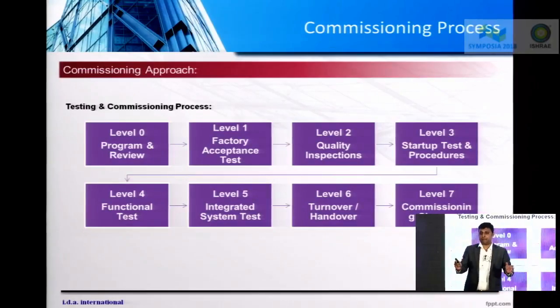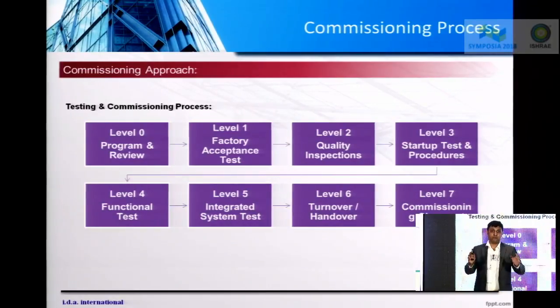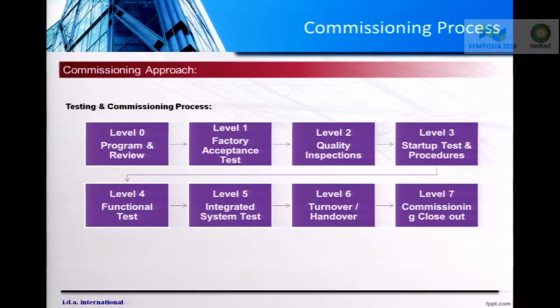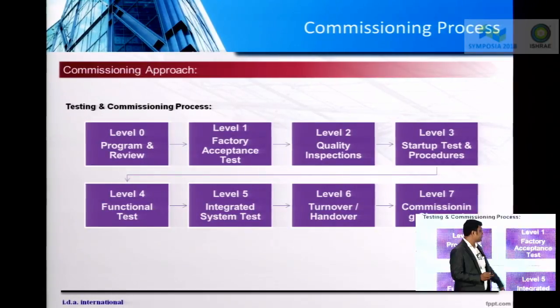Let's take an example of one single project. We would like to divide that project into 8 levels. Level 0 is program and review. Level 1 is factory acceptance test. Level 2 is quality inspections. Level 3 is startup test and procedures. Level 4, functional test. Level 5, integrated system test. Level 6, turnover and handover inspections. And level 7, commissioning closeouts. So let's understand each step one by one.